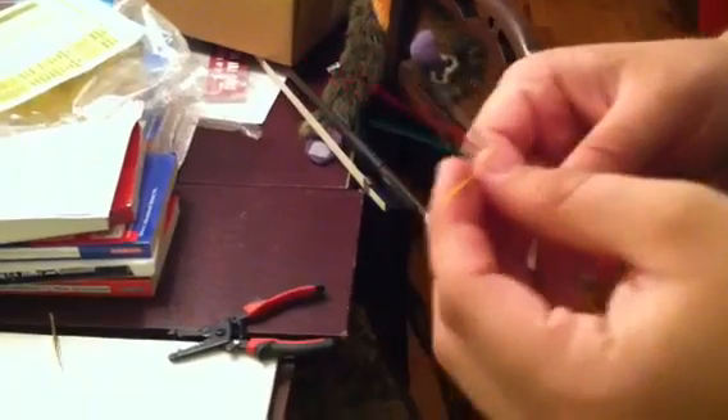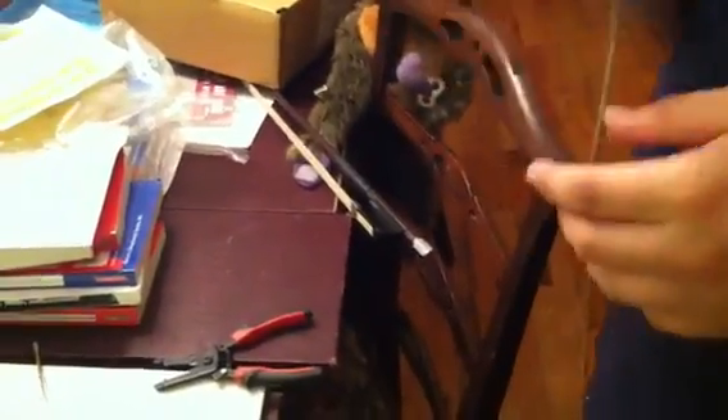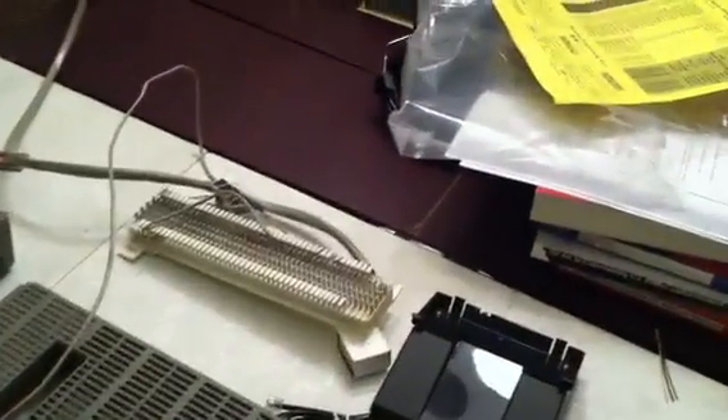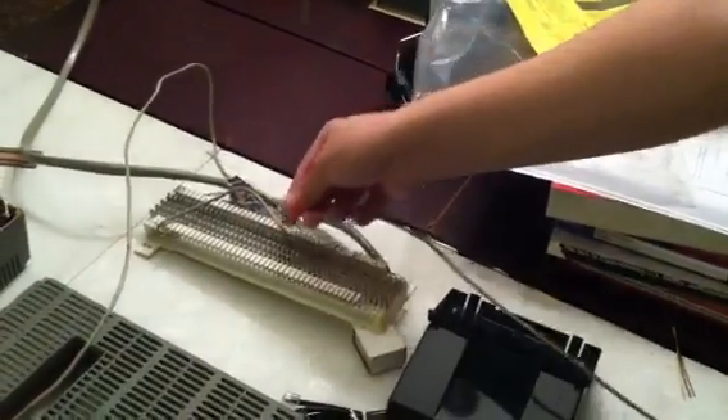Right now the inside of the wire looks like this. You have your yellow cable, your green, your red, and your black. This all goes punch down on your 66 punch block. The green always goes first, then the red, then the black, then the yellow.